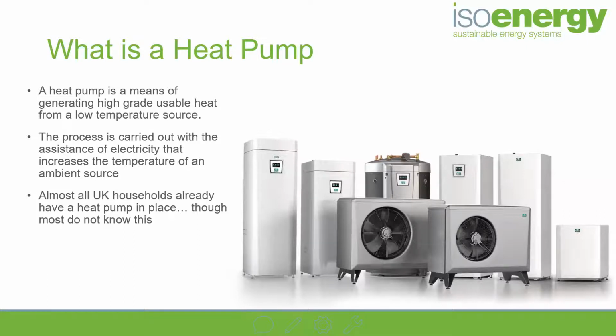What a heat pump is doing is it's using electricity to amplify ambient energy that's found in the environment. And it can be taken from a series of sources. So air source, of course, taking energy from the air. Ground source, name almost a bit of a misnomer, takes energy from anything in the ground. And it can be groundwater, it can be running water, it can be underground water in the aquifers via boreholes. You could be pumping water out of the ground through an open loop borehole system. It could be horizontal pipe work buried in the ground if you have paddocks or fields. So there's many different ways that the heat pump can take energy out of the environment, which will be covered in the seminar next week. But we'll go through a few of them today, just touch on them briefly.